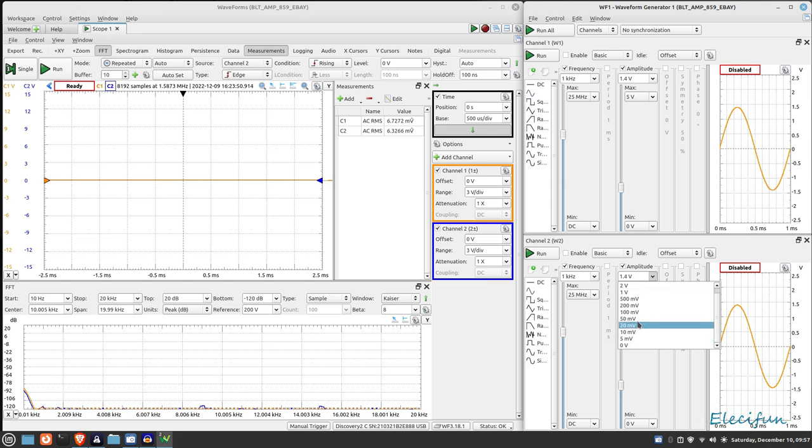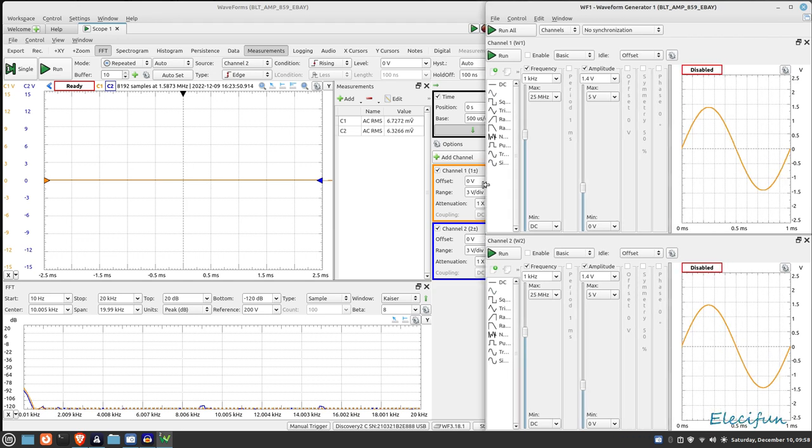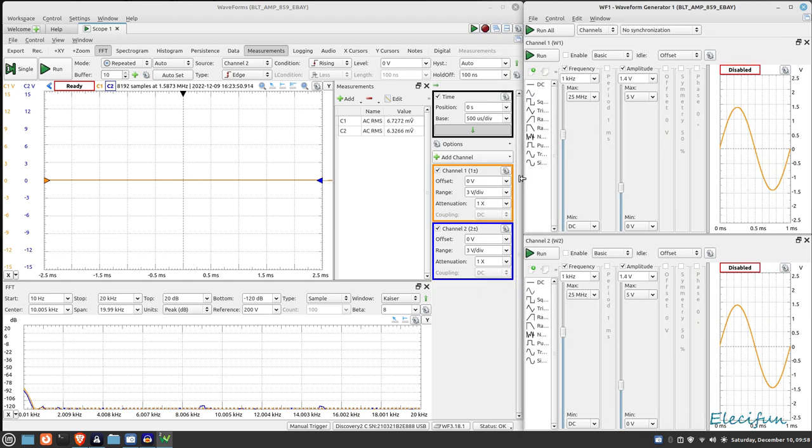I can either adjust it by the presets that it's got here or I can do it by just clicking in and typing in whatever value I choose. This is the waveform on both of them. You can see it says disabled at the moment so we've not set them off running.